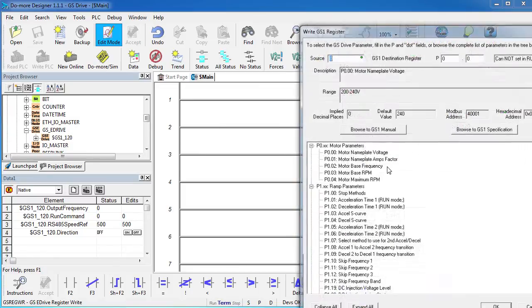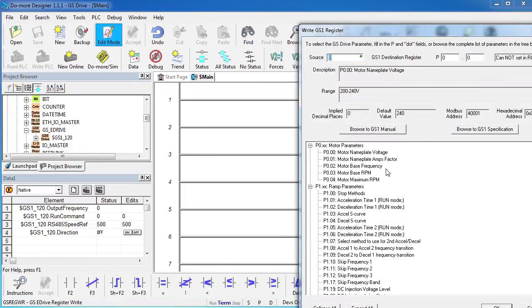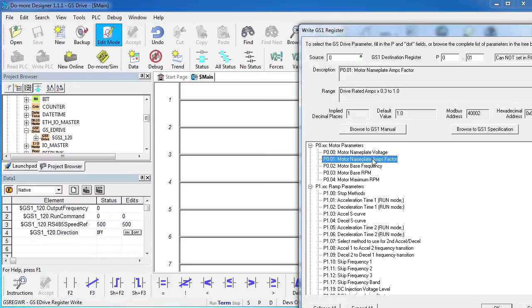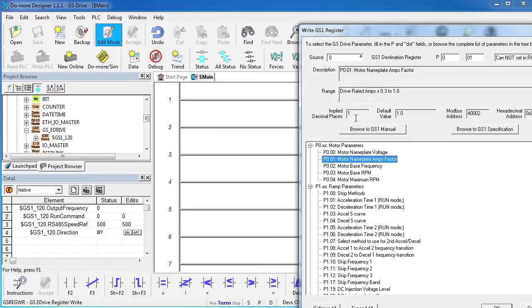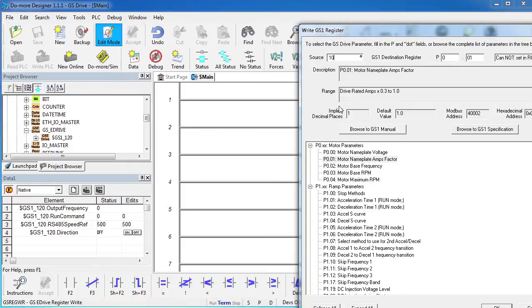Let's do another one. Let's do the amps factor this time – and I can see that the rated amps can go from .3 to 1.0 – I see the name of the parameter – but look here. The implied decimal places – there's one implied decimal place. So if I want to set this to 1.0, that means I need to put a 10 here. So how cool is that? All the information you need to correctly set a drive parameter is right here in front of you.